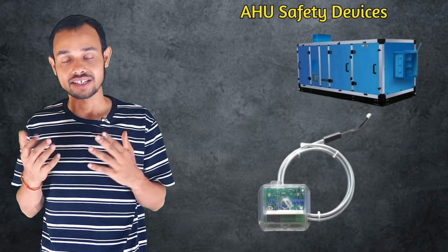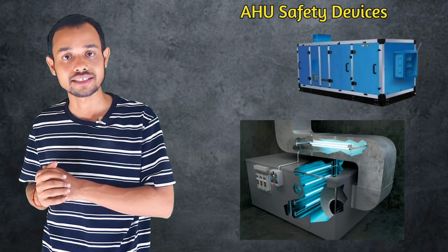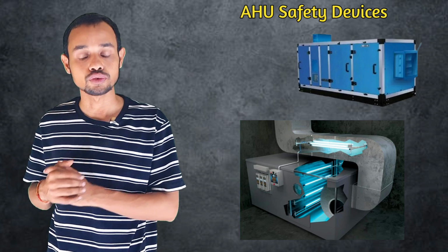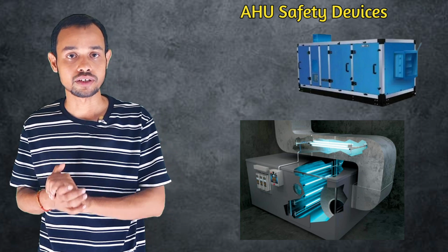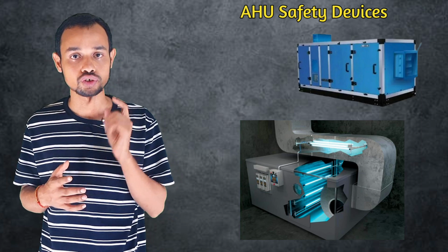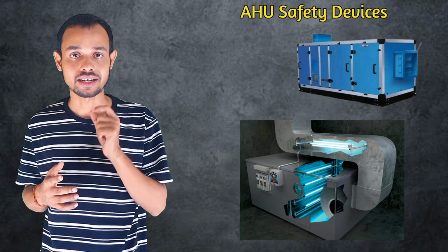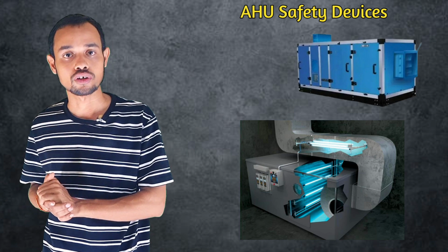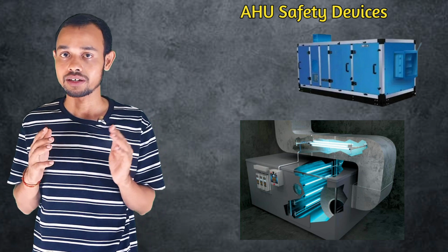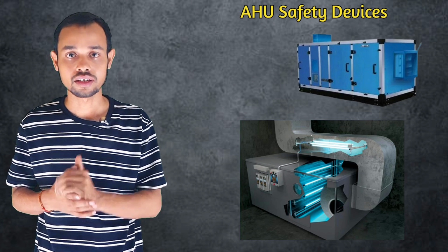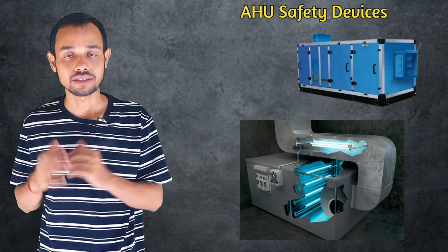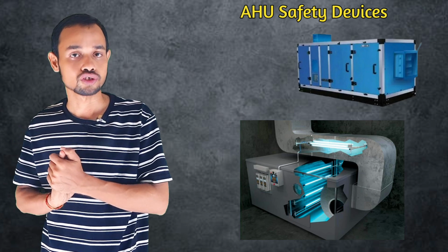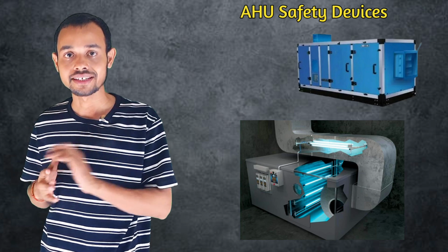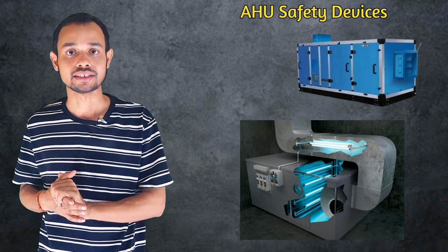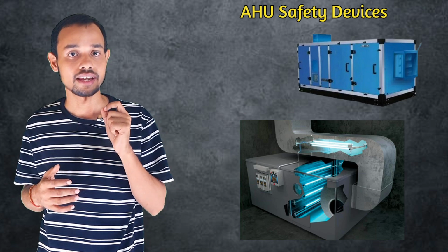And let's see the next, the sixth protection, the UV light safety interlock. What is the usage of the UV light safety interlock? Some AHUs have UV germicidal lamps. The safety interlock ensures that the lamps automatically switch off when the cover of the UV lamp is opened. Let's see the usage of this: technician safety, yes, protection from UV exposure.